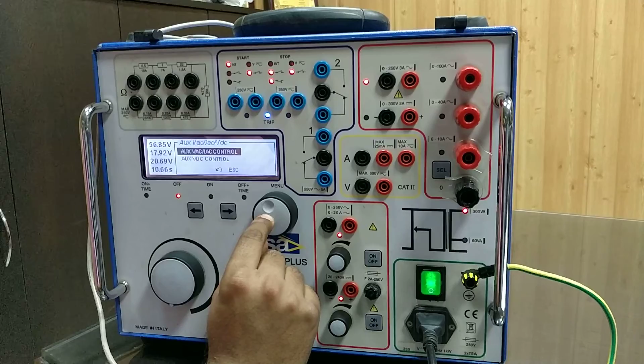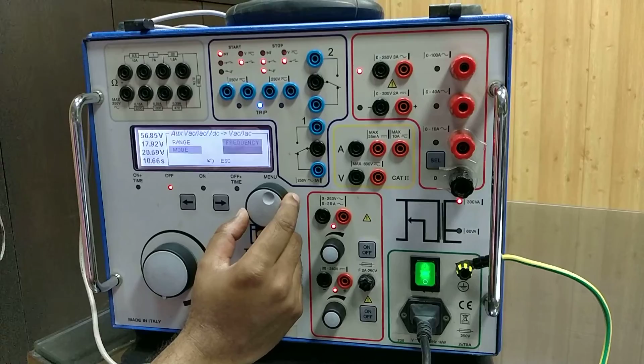In the same way, auxiliary AC also has the variation of the phase angle and frequency. These features we can access by selecting auxiliary AC and auxiliary AC voltage. And here in auxiliary AC voltage and auxiliary currents, we can select different modes as well as a frequency, and we can adjust the frequency to different values for applications like under frequency as well as over frequency.